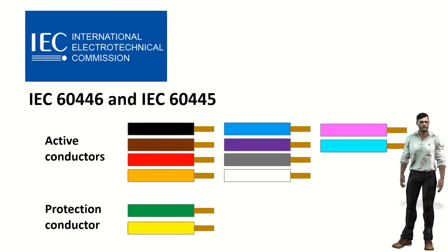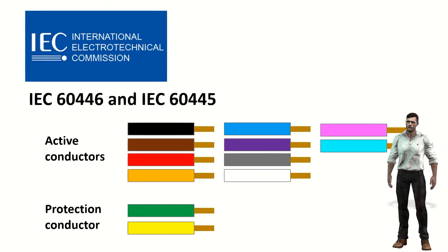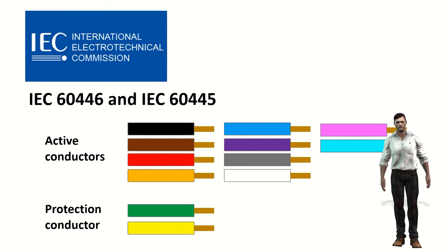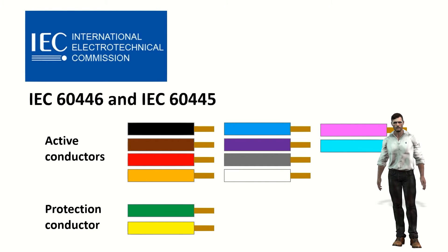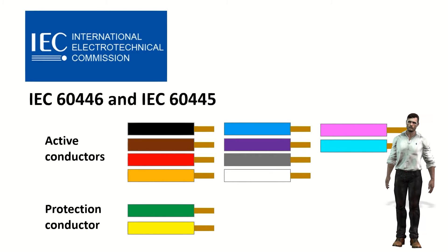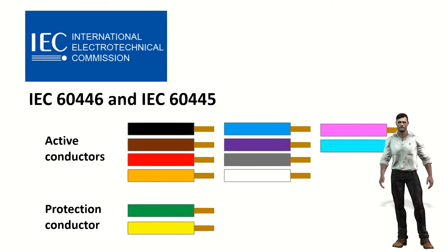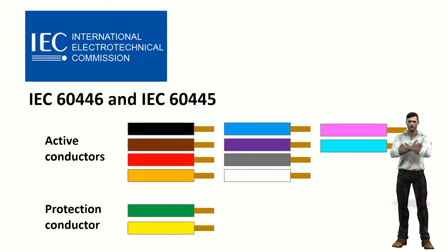As commented at the beginning, the International Electrotechnical Commission, IEC, through the IEC 60446 and IEC 60445 standards, establishes its own color coding of cables in electrical installations. This standard allows for active conductors colors such as black, brown, red, orange, yellow, green, blue, purple, gray, white, pink, or turquoise. Of which, green and yellow are reserved for the protective conductor.